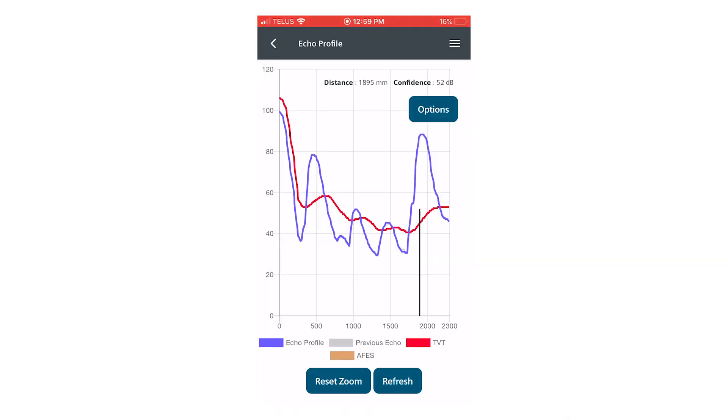This is the echo profile screen within the app and we have a false reflection appearing at about 500 millimeters and multiples of that reflection occurring at 1,000 and 1,500 millimeters.